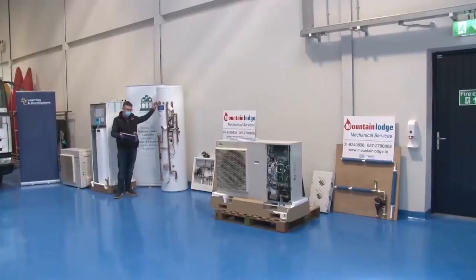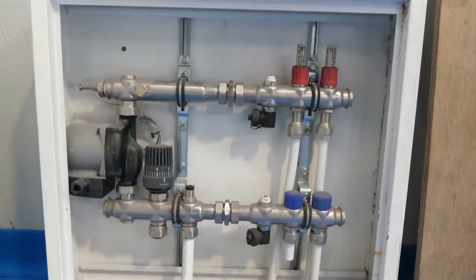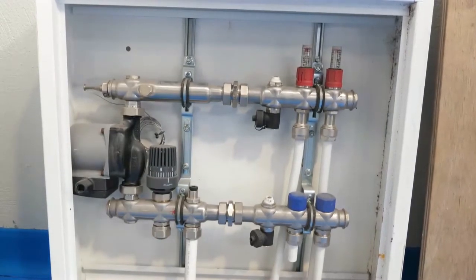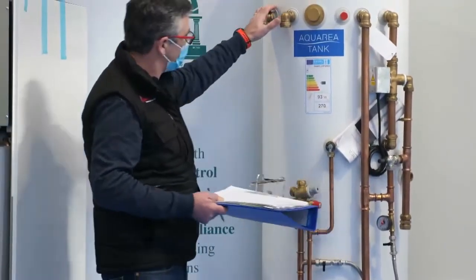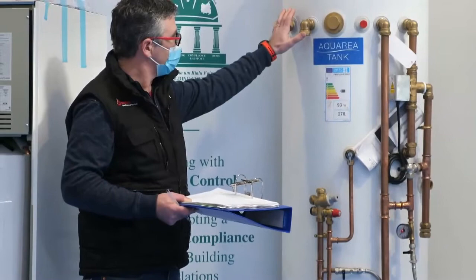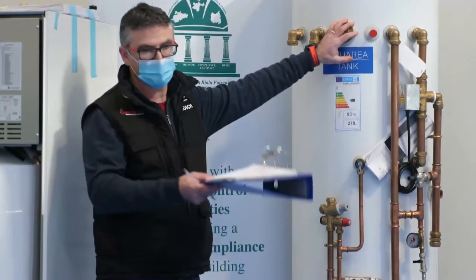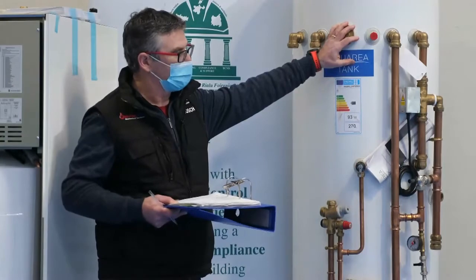You don't want heating, so it allows the unit to keep circulating a little bit through the house. There are other ways of doing it with a bypass valve, but for the moment, this is the one we're looking at. So it's heated hot water. We're now at the top. This is off to the heating system, to the radiators, to an underfloor manifold, whichever. It's after this area where your zoning comes into place, where you have to zone your living area and your bedrooms. Some of them will have an immersion here, a backup immersion if the heat pump isn't performing in extremely cold weather, so they have the facility to bring in the immersion.